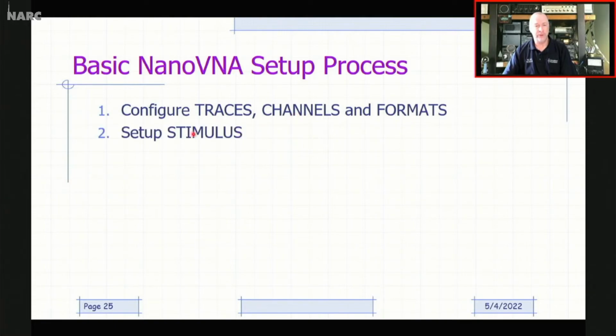So once you get that configured, you set up the stimulus. What frequency range do I want to make the measurements over? And the reality is you can do that in either order. You can do the stimulus first and then configure the traces, or vice versa. It doesn't really matter. But once you get that all defined, that's when you run the calibration. In fact, once the stimulus is defined, you can run the calibration. You can even change traces and channels and formats later as well. But once the stimulus is set, that's when you're going to do a calibrate and save.